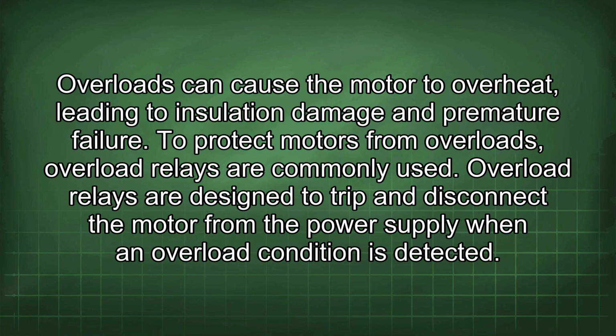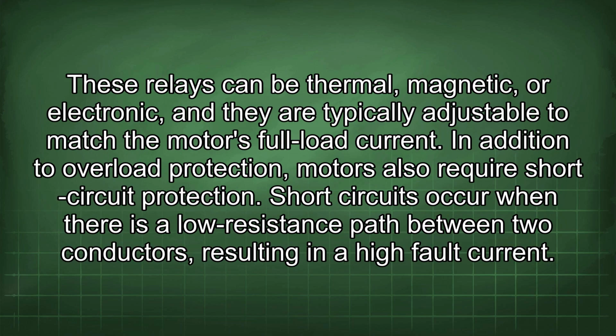To protect motors from overloads, overload relays are commonly used. Overload relays are designed to trip and disconnect the motor from the power supply when an overload condition is detected. These relays can be thermal, magnetic, or electronic, and they are typically adjustable to match the motor's full load current.